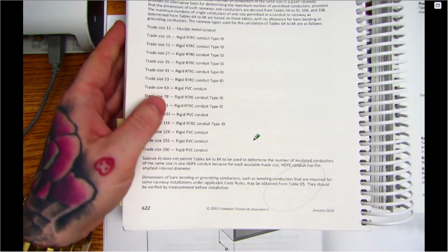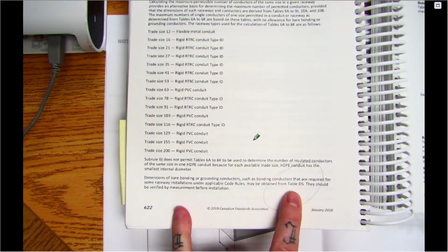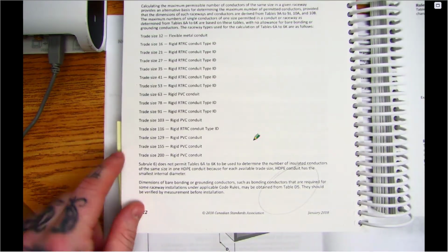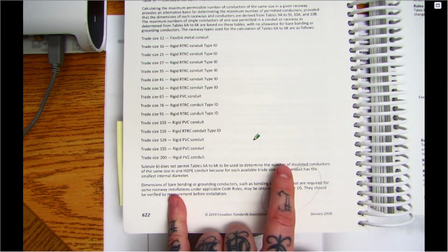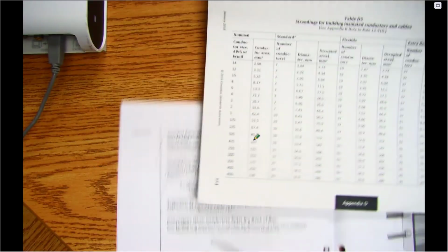And then I'm going to get to table D5 here and see exactly, well first here I'll show you what it says. Dang, that was bright. This is where it's telling us to go to table D5. Under rule 12-910, flipping over here, at the bottom it's telling us to go to D5 for that measurement for that stranded. So I'm going to go to table D5 just so we can see where they got that number in the module, so that we have an understanding.